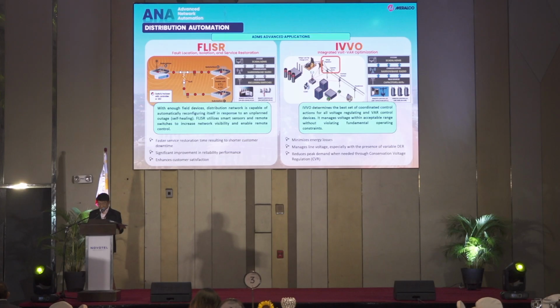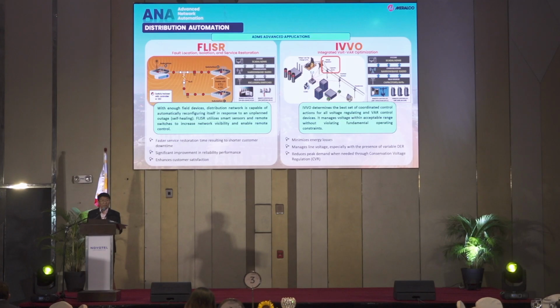On the other hand, IVVO, or Integrated Volt-VAR Optimization, also an application in ADMS, determines the best set of coordinated control actions, such as how many line capacitors or substation capacitors should be in or out. The objective is to minimize loss and manage voltages within an acceptable range at all points of the feeder and at all loading conditions. It can also be used in an advanced stage of reducing system demand, although we haven't tried this yet, through voltage conservation without sacrificing the regulated service level.